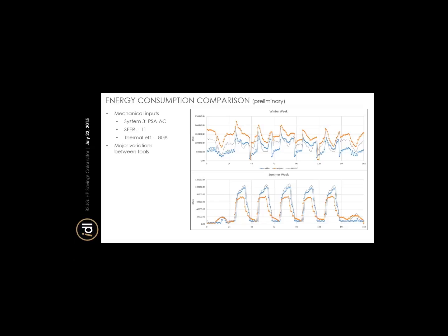Again, in the summer, you can see that there's a pretty big difference between EnergyPlus and eQuest, but this time we're tracking more with EnergyPlus rather than eQuest, which is likely due to the fact that we used EnergyPlus for our simulations to get our energy consumption data. So you can see if we're plugging in the same loads, we should get out something similar to EnergyPlus.